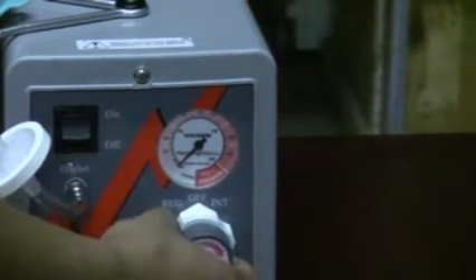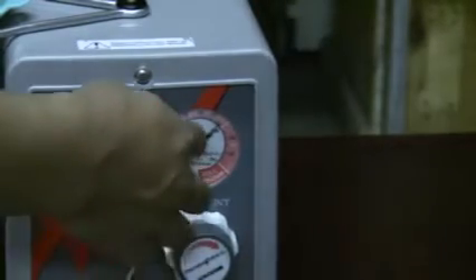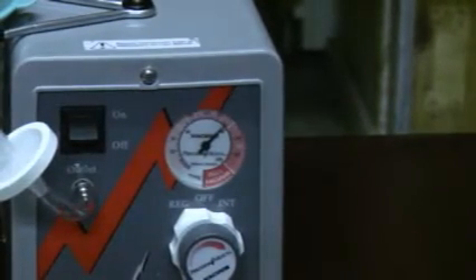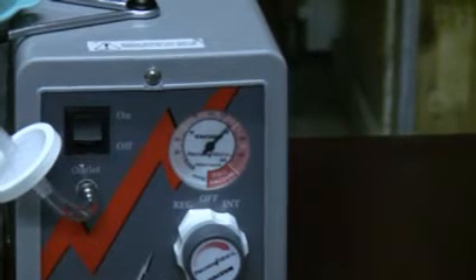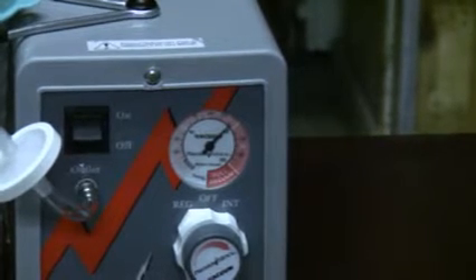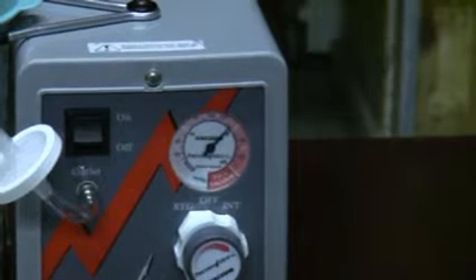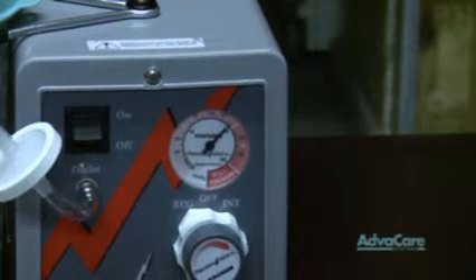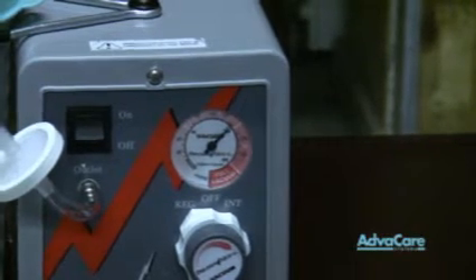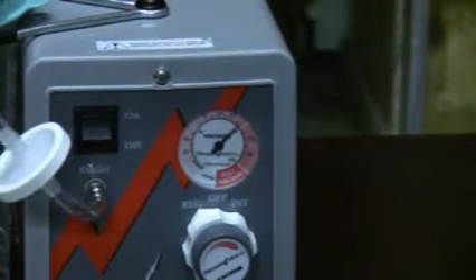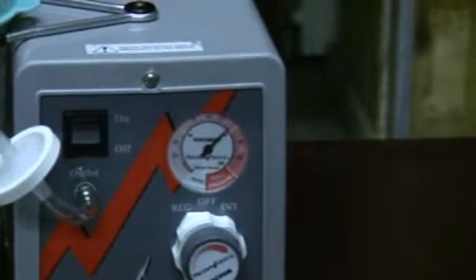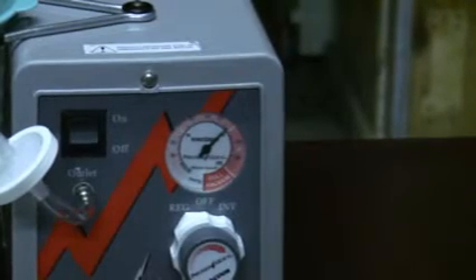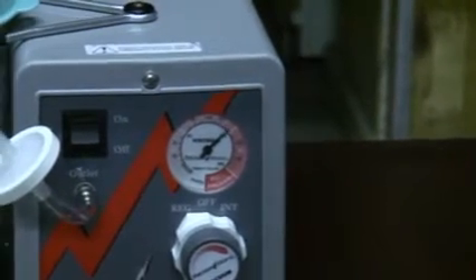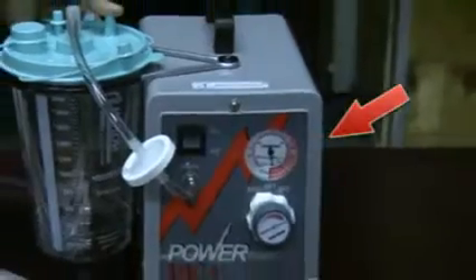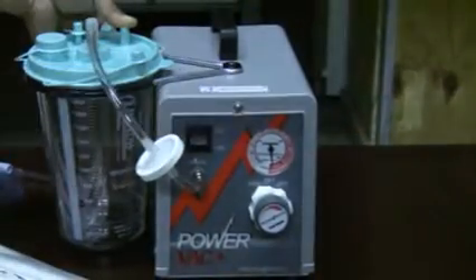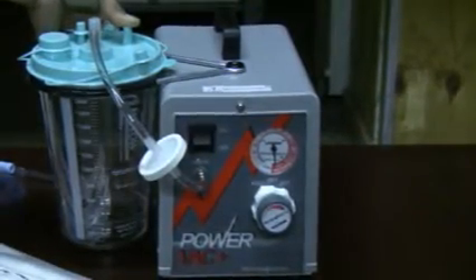Once you select regular, you may start to see some pressure on your vacuum gauge. However, if any of your ports are opened, you will not get proper vacuum suction pressure. This can be demonstrated by covering the open port at the top of your canister lid, and you can see your vacuum gauge needle go up to full vacuum.